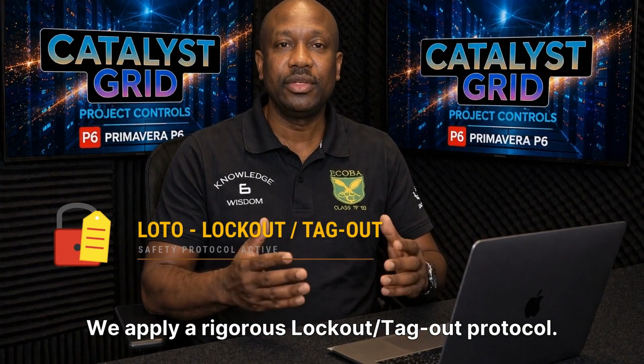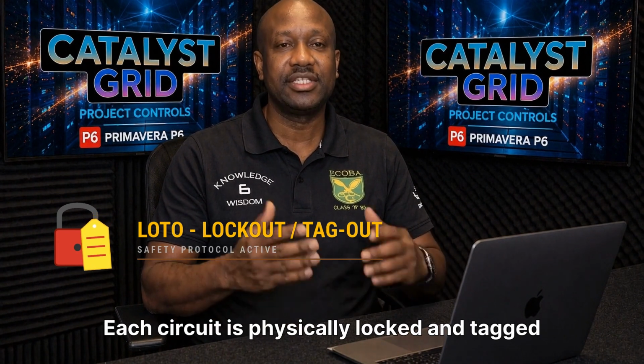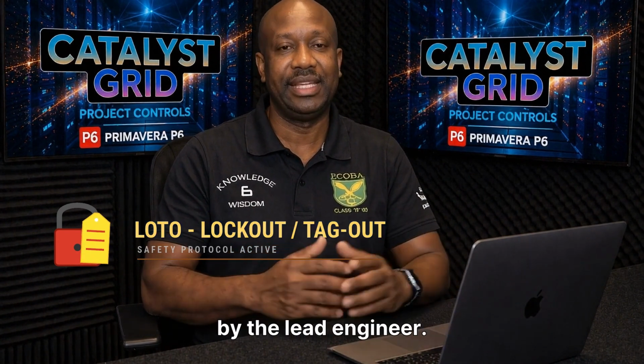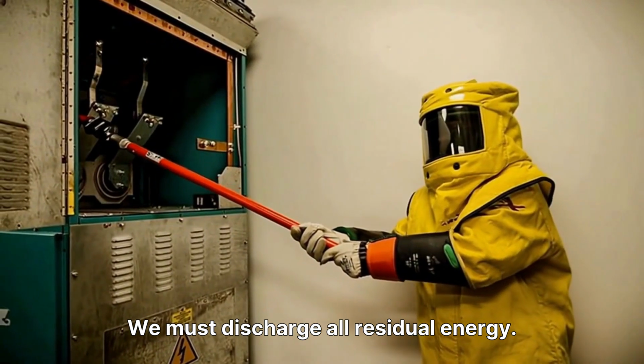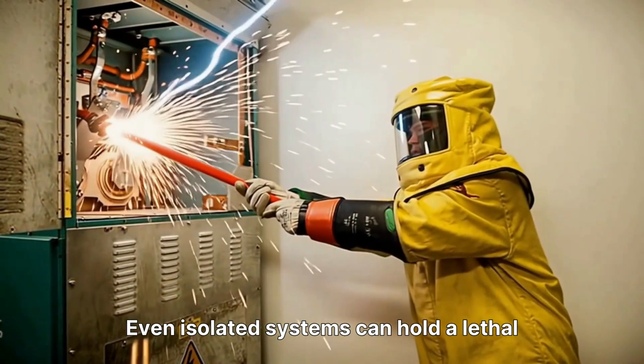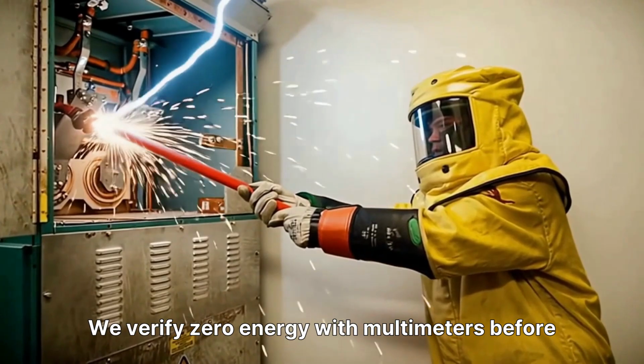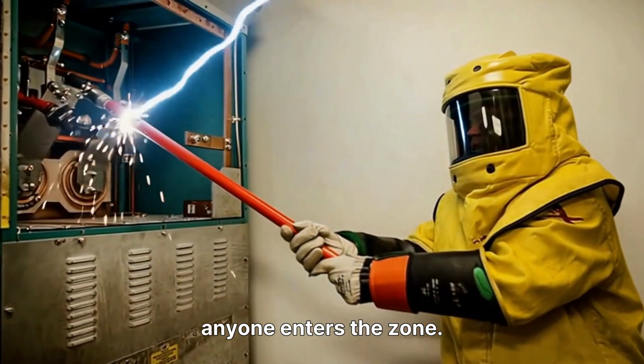We apply a rigorous lockout-tagout protocol. Each circuit is physically locked and tagged by the lead engineer. We must discharge all residual energy. Even isolated systems can hold a lethal charge. We verify zero energy with multimeters before anyone enters the zone.